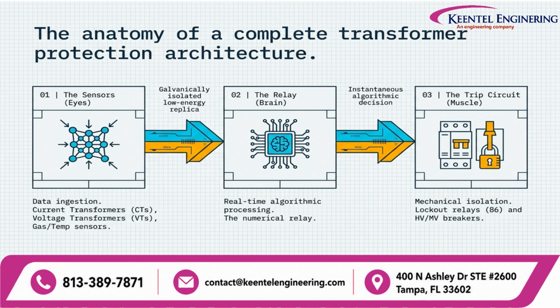It determines whether the electrical conditions represent a fault, an abnormal operating condition, or a normal transient. The third layer is the trip circuit. Once the relay determines that a genuine fault exists, the trip command must travel through the control system and operate the appropriate mechanical isolation devices. This includes lockout relays, commonly designated as 86 relays, and the high voltage or medium voltage breakers. So the complete protection chain is measure, analyze, isolate. A failure anywhere in that chain can compromise the entire protection scheme.